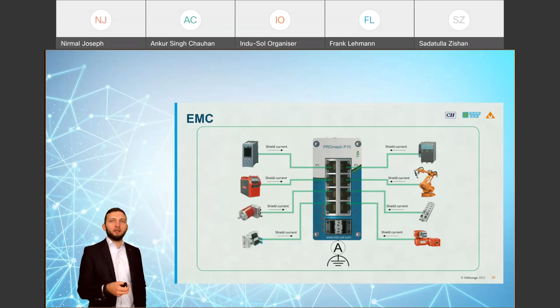And the last one is the EMC measurement. Again, we have our shielding current, and an infrastructure component like a switch can provide a leakage current measurement or shielding current measurement. After installation or after the first start of my plant, I have the information on how high the shielding current is. If it's in a green area, then I'm happy - I have a good installation, and I don't have to measure anything else in my network. Also, over the whole plant life cycle, I have the information on whether it's really stable, or if there's a change inside my leakage current, and then I have to do something. But I have the first information, and I can use this important information.